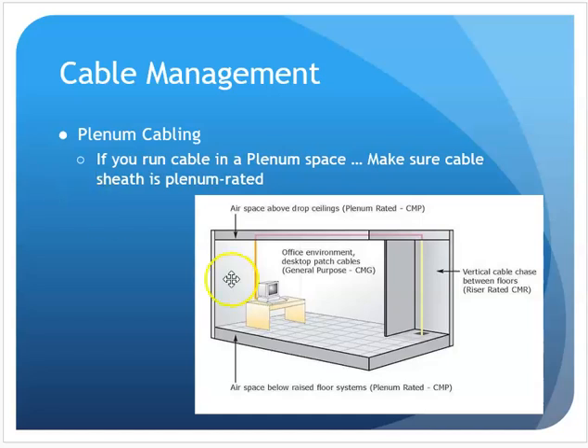As I'm routing cable, if I'm going above a ceiling and down through, like, the hallway, that could very well be a plenum space. A plenum space is where I'm moving air through a building. And if I have cabling up there and there is potentially a fire, that cable melting could be pushing toxic fumes through that hallway to another part of the building. So that area up there is what they call plenum space. So the cabling I put in there needs to be plenum rated, meaning the jacket insulation is such that the plastic, it's not fireproof. It still could burn, but the toxic fumes coming off it are going to be very minimal. The plastic is not giving off nearly the amount of toxic fumes that you would have on regular plastic insulation.